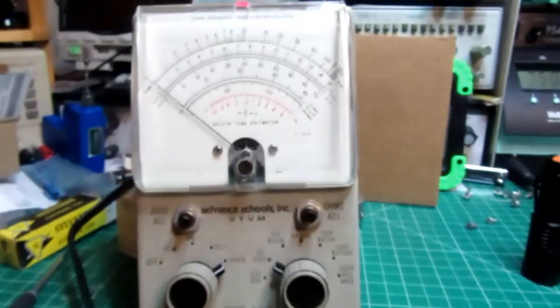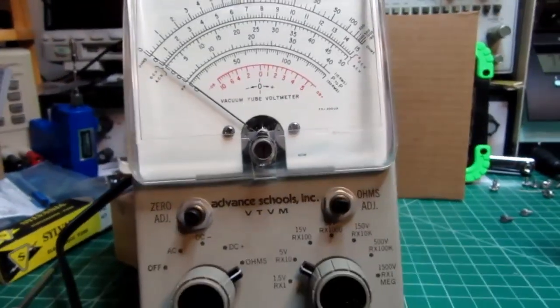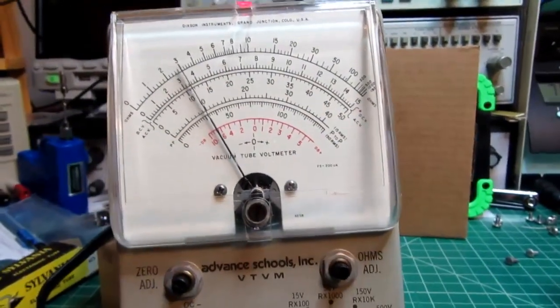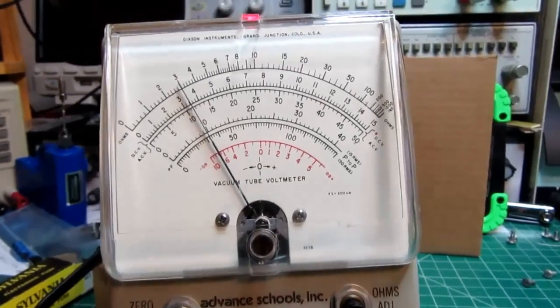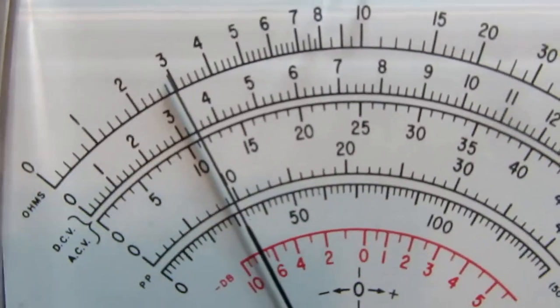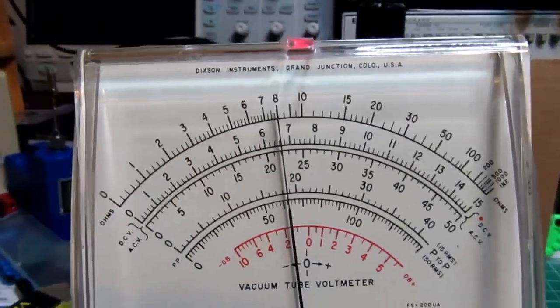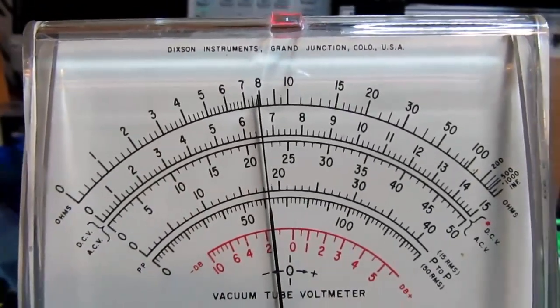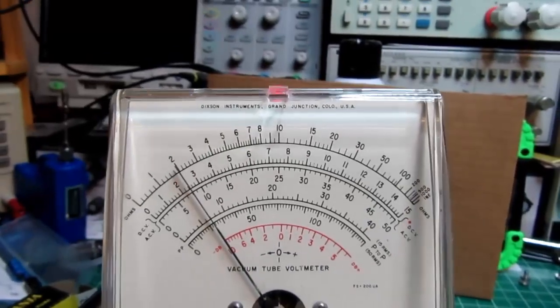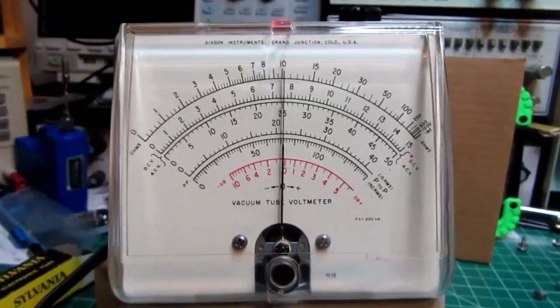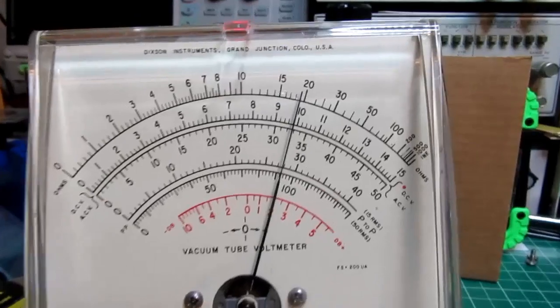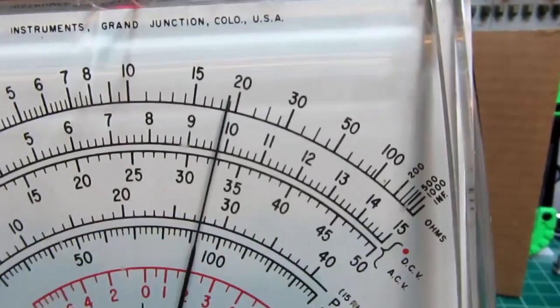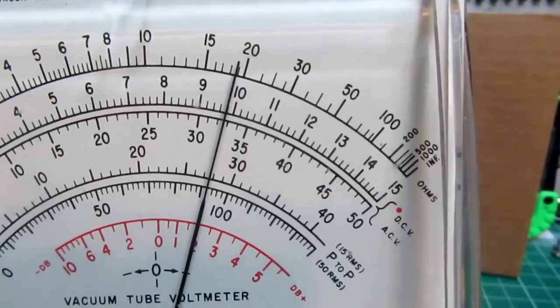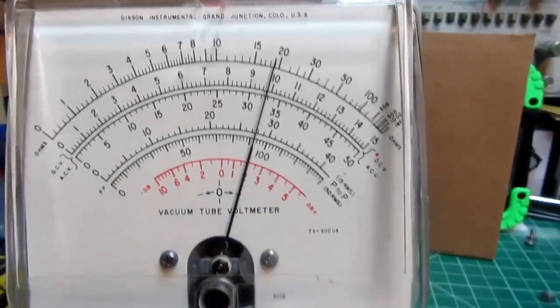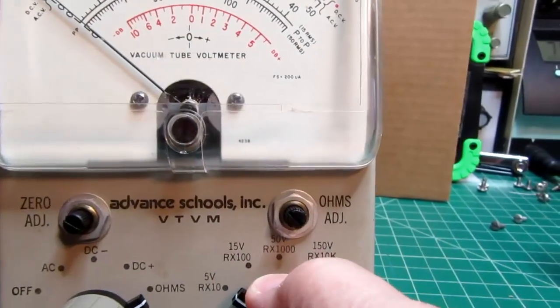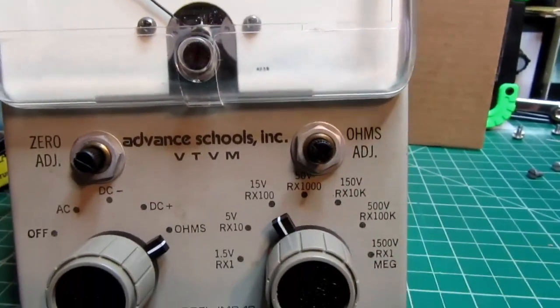Okay, so now I'm going to put in 30 ohms on the decade box, and it's right on there. Let's go to 80, pretty much right on there, so that's good. If I go to 200 ohms on the box, it's pretty close to 20 times the 10 scale, so 200 ohms. Let's go to the R times 100 range.